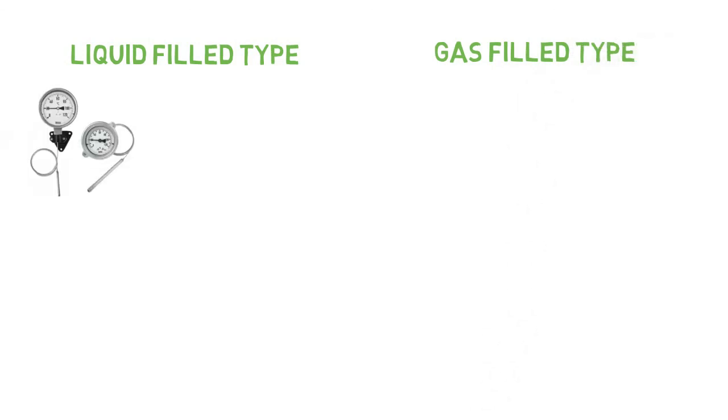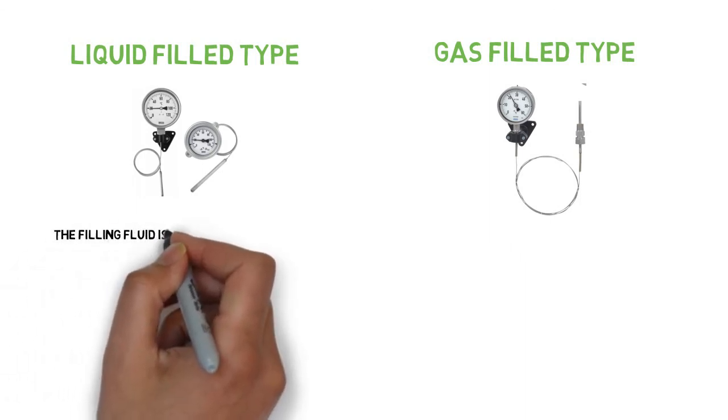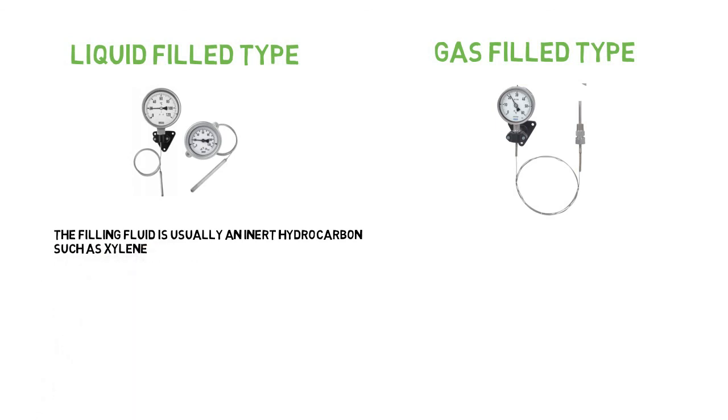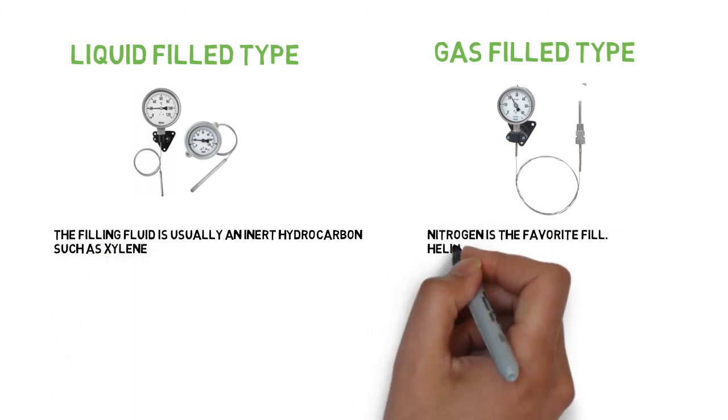Filled type system is further divided into liquid filled and gas filled type. The filling fluid is usually an inert hydrocarbon, such as xylene. Nitrogen is the favorite fill; helium is also used.